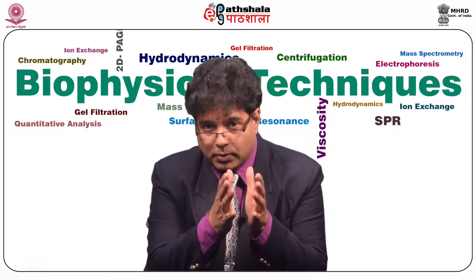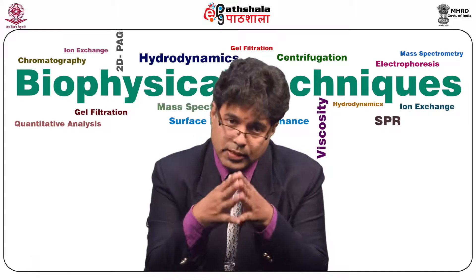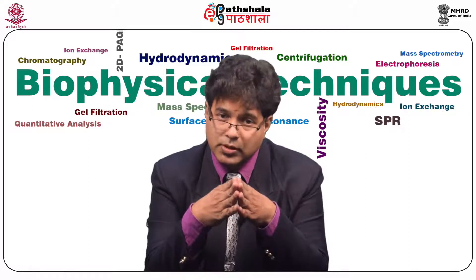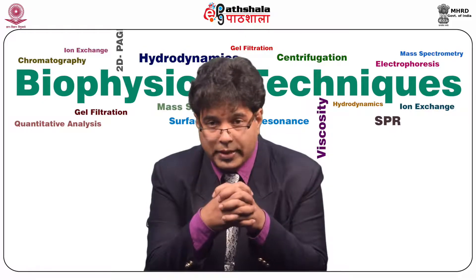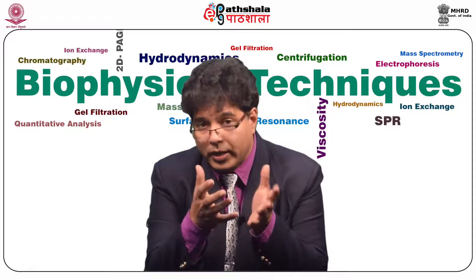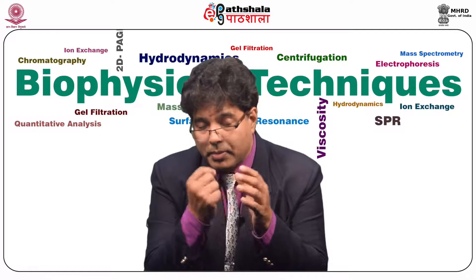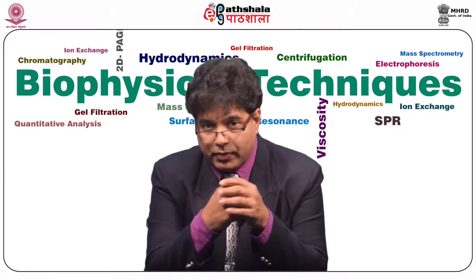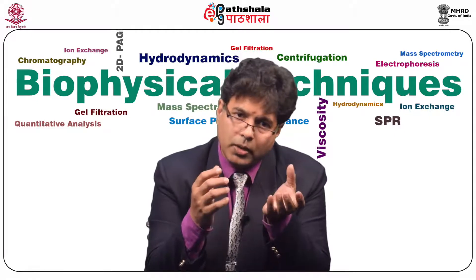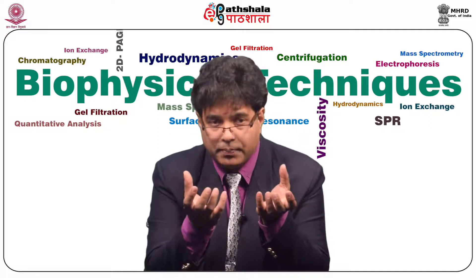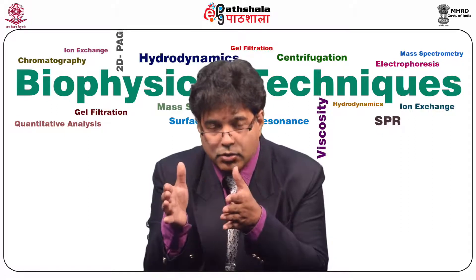Time of flight gives better resolution in the mass spectrum compared to quadrupole mass spectrometry. This allows time-of-flight instruments to obtain high-resolution data for high molecular weight compounds, including multiply protonated molecules like proteins or peptides, which can be accurately measured and quantified. Quadrupole mass spectrometry is predominantly used for analytical purposes. Sometimes quadrupole and time of flight are coupled together to achieve better separation using the quads and better resolution using the reflectron.